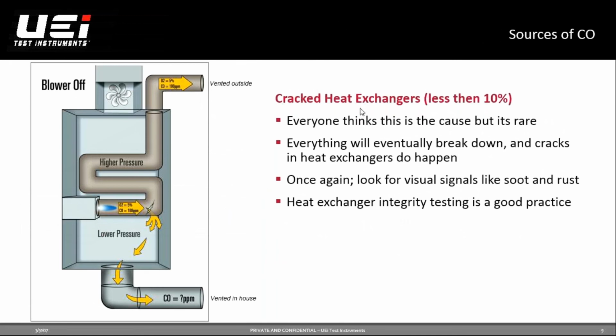So the other thing I want to talk about that's specific to the HVAC world in carbon monoxide is cracked heat exchangers. I know there's a lot of methods guys talk about to diagnose if a heat exchanger is cracked. It doesn't happen a whole lot, it's not one of the major sources of CO in a house. It accounts for less than 10% of CO alarms going off in a house. But if you're not checking for it during your clean and checks, you're exposing yourself to a whole lot of liability.